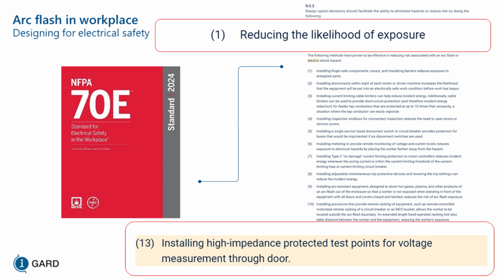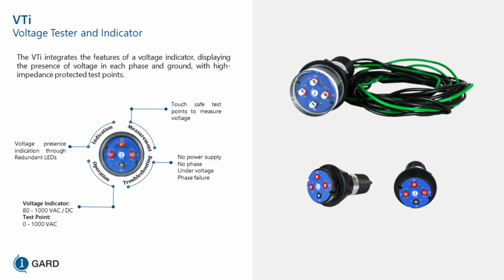So owners and consultants have the duty to design for electrical safety, for arc flash and shock. So we have to reduce the likelihood of exposure. And this year in the code revision 2024, high impedance protective test points have been introduced. And I think it's been introduced more to prevent shock than arc flash. So it allows the worker to measure the voltage and troubleshoot the circuit from outside the cell, instead of going inside the cell or opening the door to measure voltage.